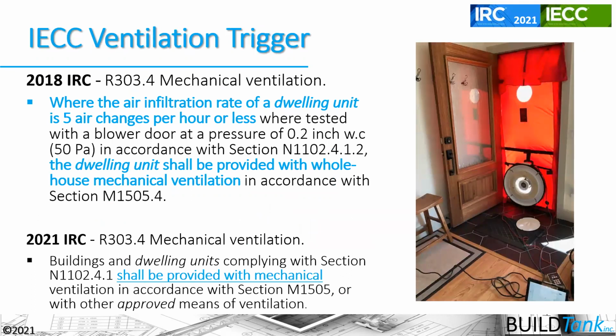So the code used to say in the 2018 and lower IRC and IECC that if your house was tighter than 5 air changes, in essence, you had to use controlled mechanical ventilation. Now in the 2021 IRC, it just says it has to be provided. It's basically been delinked from how airtight the house is. There are separate requirements for how airtight the house is. And now we need to ensure that we get that ventilation rate correct as well.